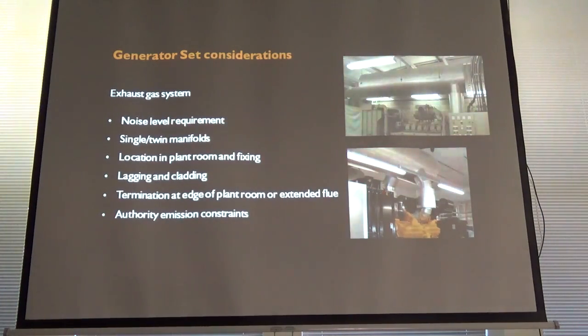Then there are silencer systems. Basically you've got the bellows and then you've got a silencer system, could be primary and secondary, could be your main silencer off each one of the V banks if it's a V unit. Then they're brought together and then they go to the secondary silencer and they're routed wherever. You keep within back pressure limits. It's like putting a banana tailpipe, exhaust pipe, on the car. It'll fire, it'll have problems. That's the thing, you keep them within the back pressure limits. Often most sets will work up to a limit of 10.2 kPa. You lose 60% probably of that overall limit within the primary, secondary silencer arrangement and turning them, and after that it's the flue system, the horizontal run, the amount of turns and everything, which then dictates overall size.